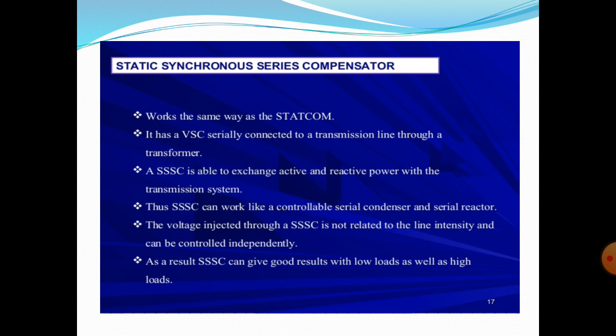Next one is the unified power flow controller, which is nothing but UPFC. This system is a combination of a static synchronous compensator, that means STATCOM, and a static synchronous series compensator, that means SSSC, which are coupled via a common DC link. This allows bidirectional flow of real power between the series output terminals of the SSSC and the shunt output terminals of the STATCOM, and they are controlled to provide concurrent real and reactive series line compensation without an external electric energy source.